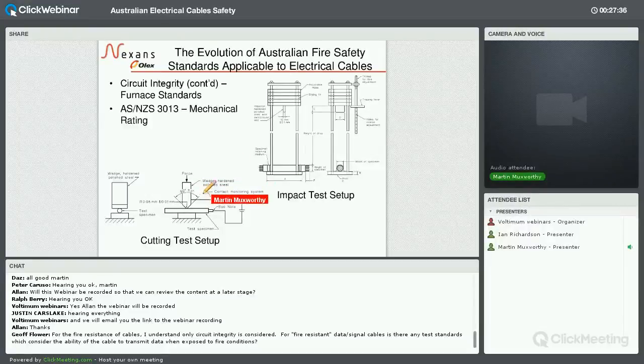In the case of the cutting test, the cutting tool is a small wedge that's applied with a compression testing device, and again, similarly, the force is monitored and controlled to apply a certain force depending on the cable size and the category that you wish to meet. So that's how the mechanical side of the 3013 test is determined.